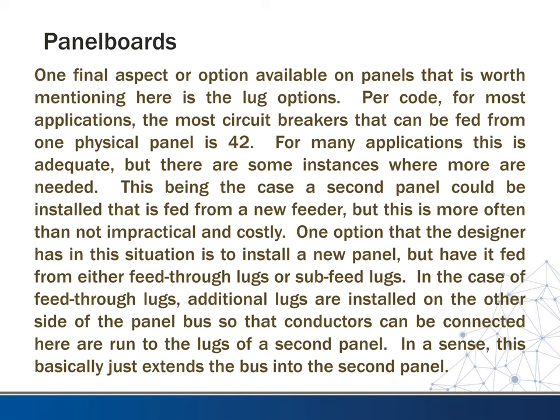One option that the designer has in this situation is to install a new panel but have it fed from either feed through lugs or sub-fed lugs from the original panel. In the case of feed through lugs, additional lugs are installed on the other side of the panel bus so that the conductors can be connected here and run to the lugs of the second panel. In a sense, this basically just extends the bus into the second panel.